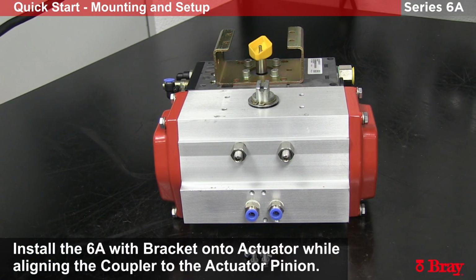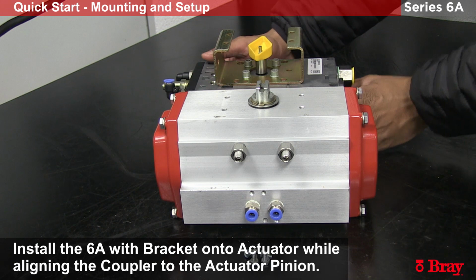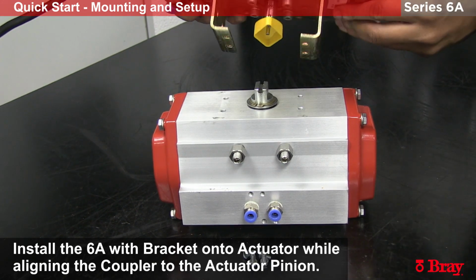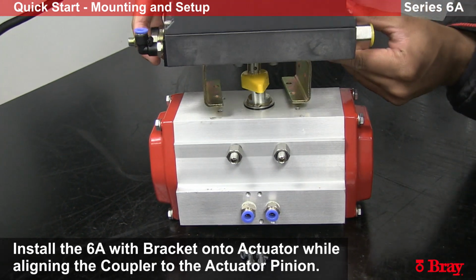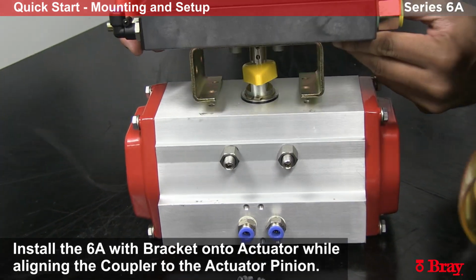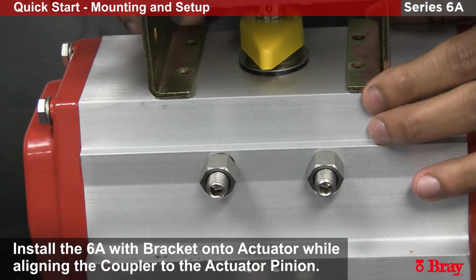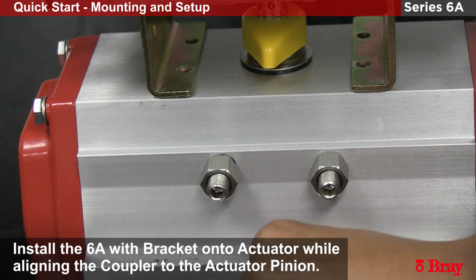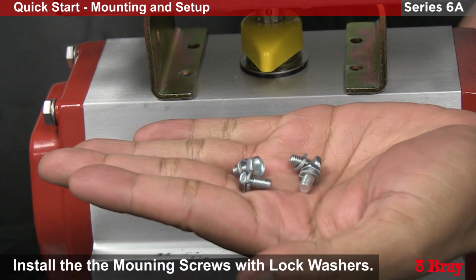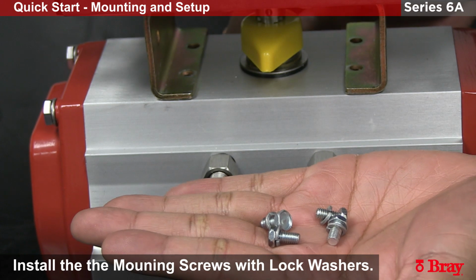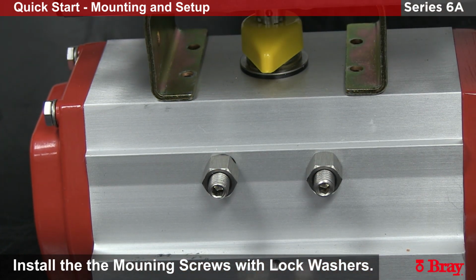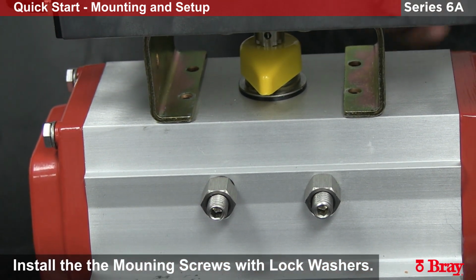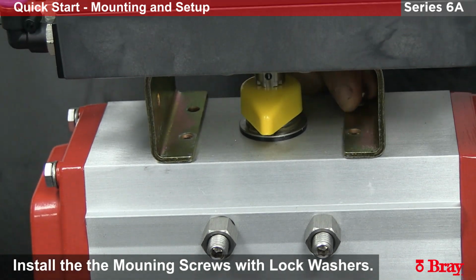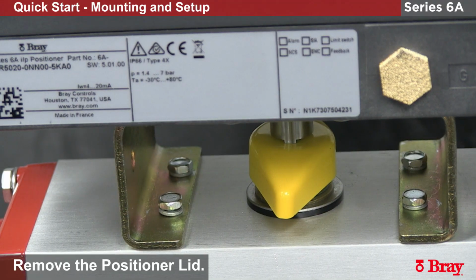Now we can place the positioner and bracket onto the rack and pinion actuator. To do this, we'll lay the positioner on top, making sure the coupler links up to the pinion of the actuator. We will then use the supplied 4 hex bolts to mount the bracket to the actuator. With the bracket now attached to the actuator, we can begin to set the transmissions on the positioner.